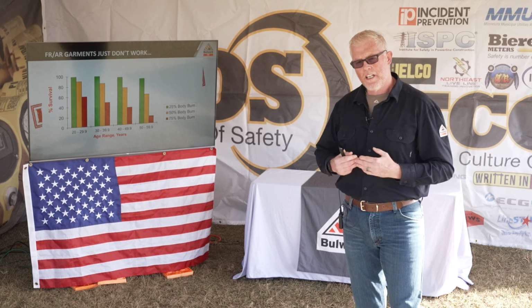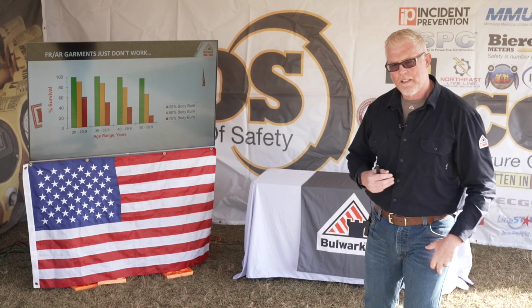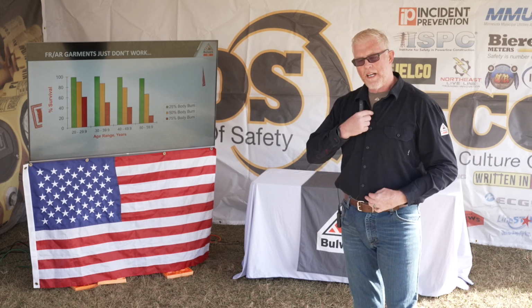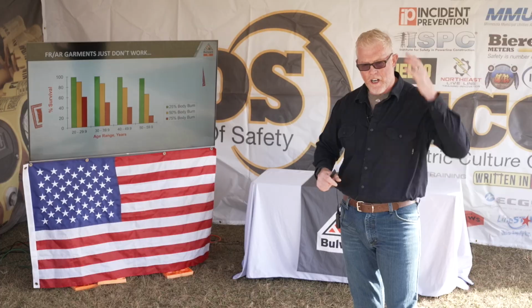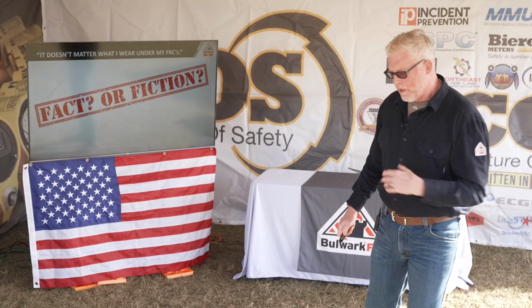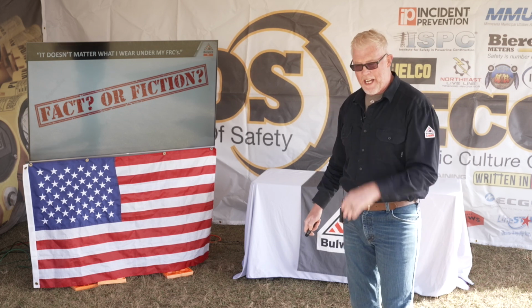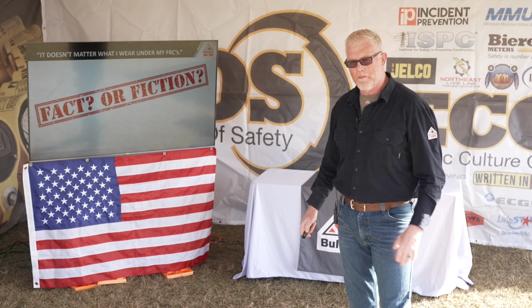So if you're wearing a flame-resistant, arc-rated pant and shirt, buttoned up to the neck, secured at the wrist, with a hard hat, safety glasses, hearing protection, rubbers, and leathers as an electrician—is there 25% of me showing? Can I injure 25%? No, it's significantly less. That's how we can categorically say if you're wearing good stuff, taking care of it, and wearing it correctly, 100% of the time there will be no fatality, because there's not enough of you exposed to hurt in these situations. Once I get this stuff on, I'm bulletproof, I'm Superman—it doesn't matter what I wear underneath my FRCs, I'm going to be good to go.